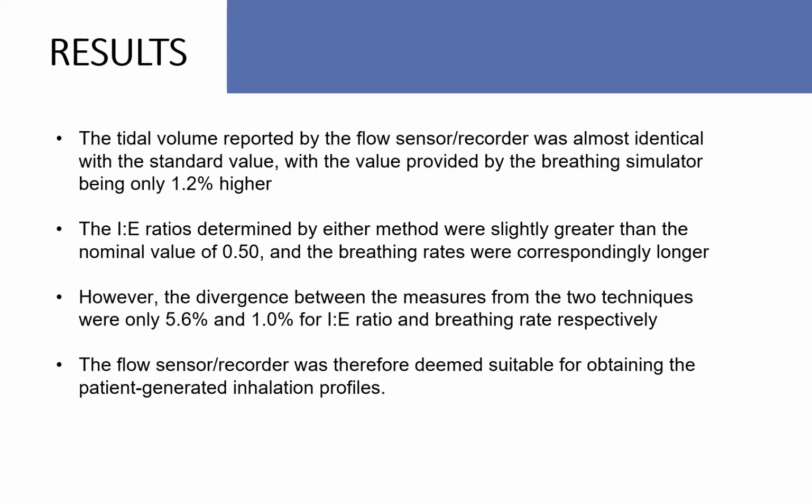Tidal volumes reported by the flow sensor recorder are almost identical to the standard value. However, the value provided by the breath simulator is about 1.2% higher. IE ratios determined by either method were slightly greater than the nominal values of 0.5, and breathing rates were correspondingly longer. However, the divergence between the measured values of the two techniques was only 5.6% and 1.1% for the IE ratios and breathing rate respectively. This may be a result of the sampling frequency between the breath recorder and the ASL.